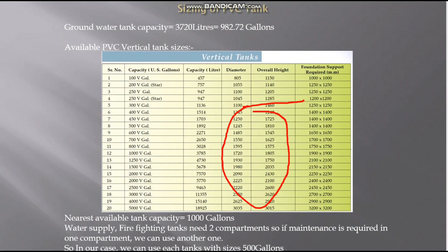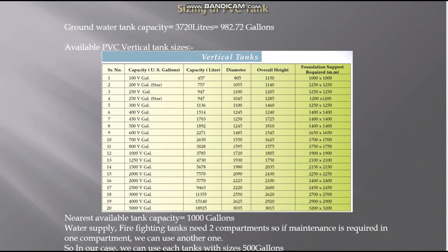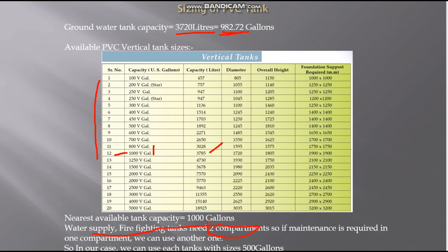For PVC tank sizing, we use the same required capacity of 3,720 liters, which equals 982 gallons. Checking the manufacturer's data sheet for available sizes, 982.72 gallons falls between the 800 and 1,000 gallon options, so we select the next size up: 1,000 gallons, which equals 3,785 liters. Since water supply and firefighting tanks must have two compartments, we use two separate tanks of 500 gallons each, giving a total capacity of 1,000 gallons.